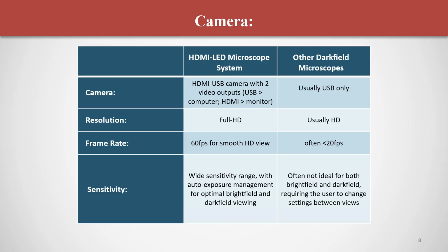Yes, just lastly, another important consideration is just the camera as well. And many of these cheaper Darkfield systems I've seen, they seem quite attractive and quite good because they often have a very high resolution camera, 14 megapixels or something like that, which seems really quite good. But there are some important things to look for there as well. The resolution is not necessarily the most important feature. Because we are looking at live samples, we're actually moving through and scanning through the sample with the client. So we have it displayed on the screen there.